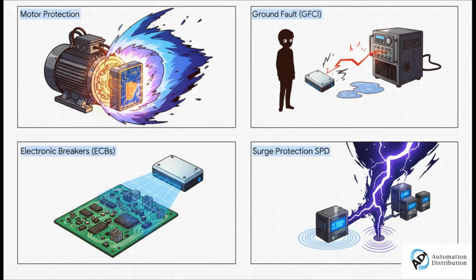For instance, motors create this huge inrush of current when they first start up, so they need special motor protectors. If you have sensitive electronics like a PLC or a computer, you'll need surge protection devices, or SPDs, to guard against voltage spikes. For personnel safety, especially around outlets, ground fault circuit interrupters, or GFCIs, are non-negotiable. And for today's modern panels that are packed with 24-volt devices, electronic circuit breakers give you a level of smart, precise protection that a standard breaker just can't touch.